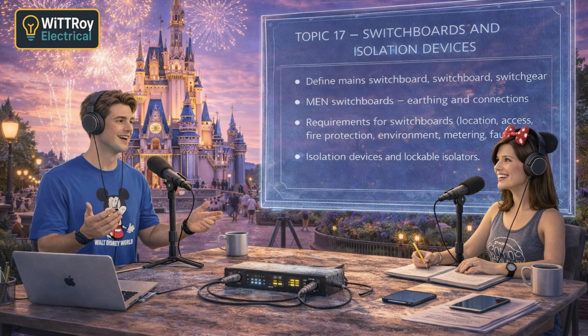Why is that so important? Because the protection system depends on it. Earth fault loop impedance relies on a low resistance path through the MEN system. So, if the connection is bad, breakers might not trip. Exactly. That's why MEN switchboards must be installed very carefully. Okay, that sounds serious. It is.